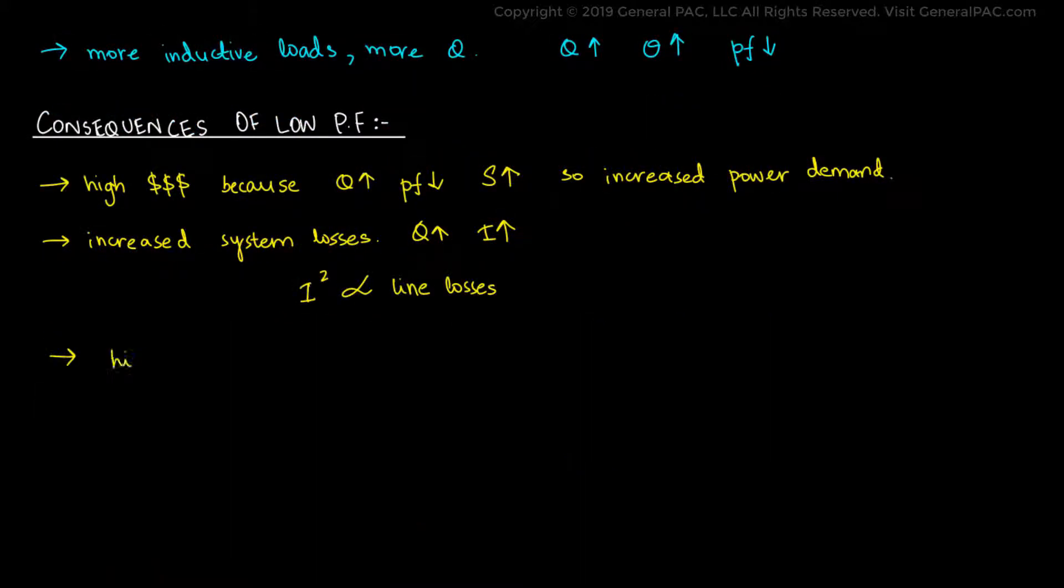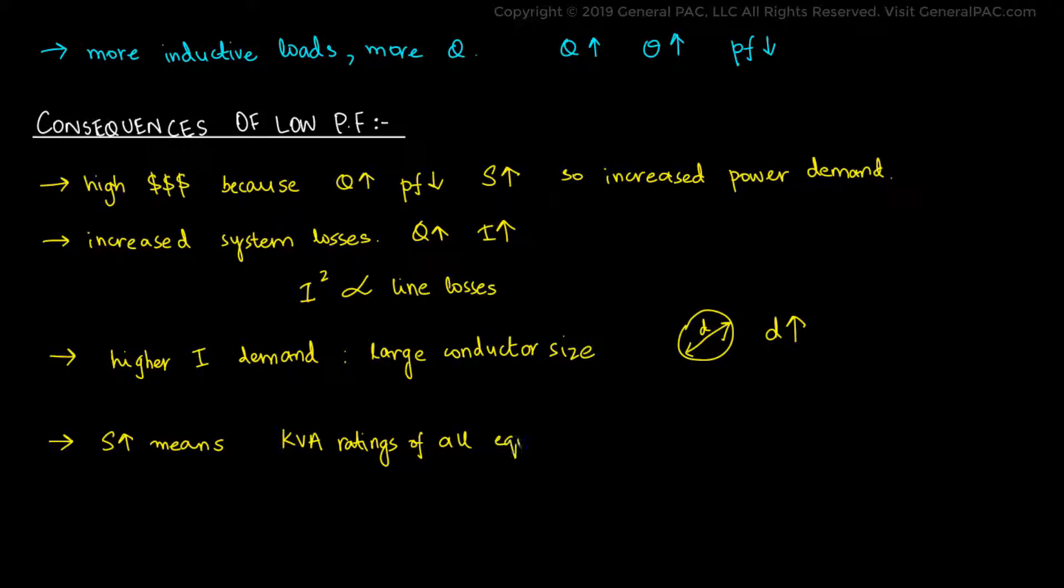In addition to that, the higher current demand would mean that a larger conductor size would be required to safely transmit power throughout the system. Furthermore, the increase in overall apparent power would mean that the KVA ratings of each equipment present in the facility would need to be increased as well. This adds unnecessary design costs to the system which can easily be avoided with a high power factor.